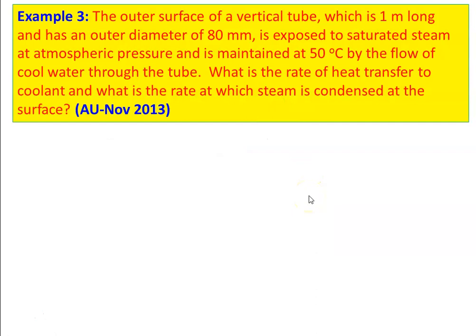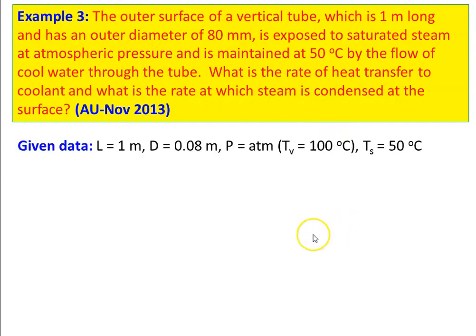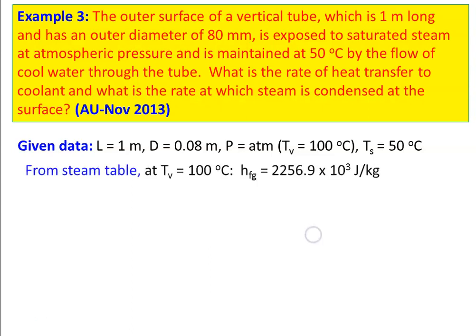Example number 3: The outer surface of a vertical tube, 1 meter long with an outer diameter of 80 mm, is exposed to saturated steam at atmospheric pressure and is maintained at 50°C by flow of cool water through the tube. Find the rate of heat transfer to the coolant and the rate at which steam condenses at the surface. Given data: length L = 1 m, diameter D = 0.08 m, steam at atmospheric pressure so vapor temperature Tv = 100°C, surface temperature Ts = 50°C. From the steam table, HFG = 2256.9 × 10³ J/kg.